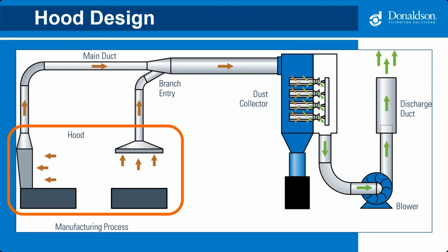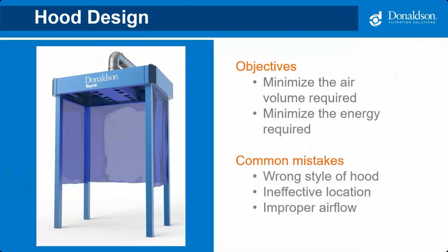So let's start at the beginning, at the endpoints, with the hoods. This is a critical component that will allow for containment and collection of fugitive dust. A well-designed hood is going to minimize the amount of airflow that's required to effectively capture and control the contaminant where it's released, while minimizing the energy required to do this. When it comes to assessing an existing system, there's a few common mistakes that I see. The wrong style of hood is being used, the hood's not located in an effective position, or you have inadequate airflow at the hood.